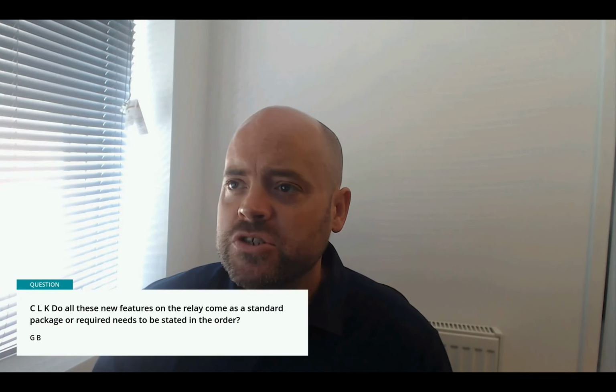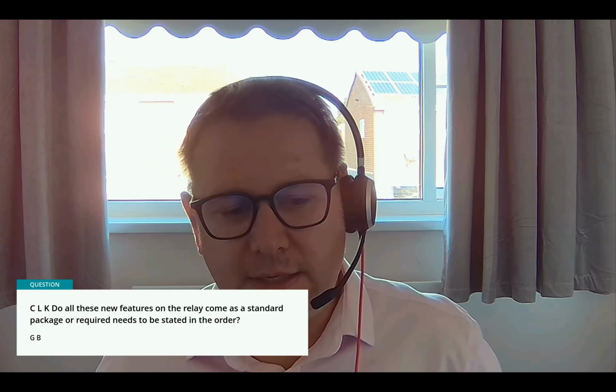Thank you, Neil. Okay, we've got another question from CLK. It says, do all these new features on the relay come as a standard package or required needs to be stated in the order? All the new protection functionality is going in as standard. The only thing, as we said, was in terms of the arc protection, the RayArc module that goes with it, the external sensors, is a separate ordering option, so it's a separate device really. But the arc flash detector software is included.